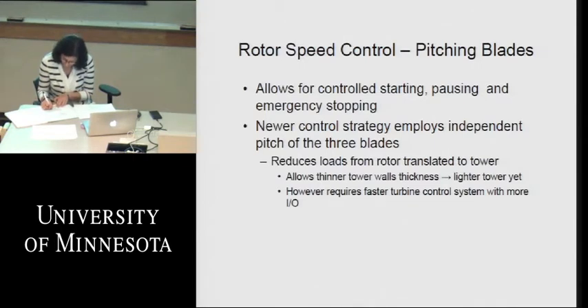So that one blade will be loaded more than the other two. Now think of it conversely with one blade at 6 o'clock and the others at 2 and 10. Now that blade at 6 o'clock is passing the tower and unloading at that point. So you're getting an uneven distribution of the thrust forces along the swept area of the rotor if you've got all three blades pitching to the same angle all the time. We can actually put in control algorithms that will learn and sense these patterns through fuzzy logic and such, so that we can reduce the total thrust forces on the tower from the swept area of the rotor very significantly. And so this is one of the newest control strategies within this blade pitching.